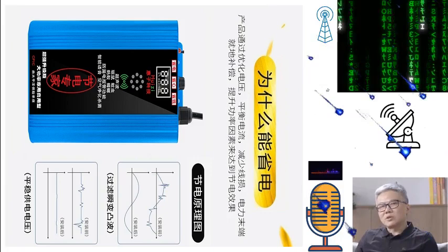The role of power factor correction. At the heart of many energy-saving claims is the concept of power factor correction. The power factor is a measure of how effectively electrical power is being used, with a higher power factor indicating more efficient use of electricity. Devices like the Superpower Energy Saving King are designed to improve the power factor by reducing reactive power, which does not perform any useful work but still contributes to the total energy consumption. While improving the power factor can lead to some energy savings, the extent of these savings depends on the specific conditions of the electrical system.